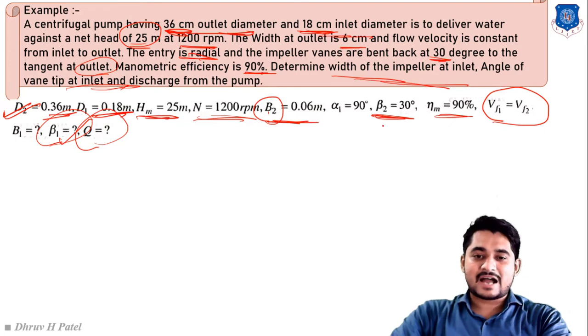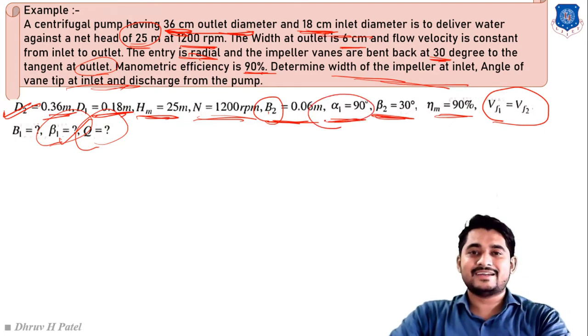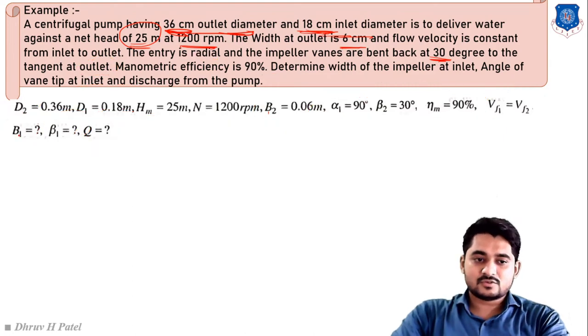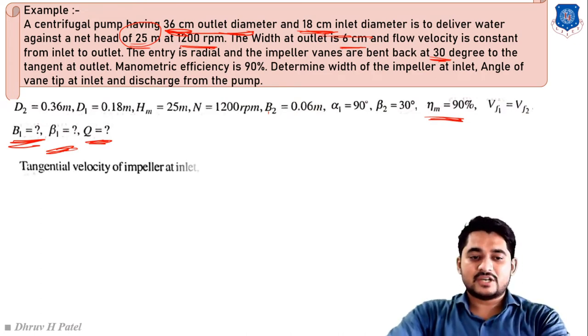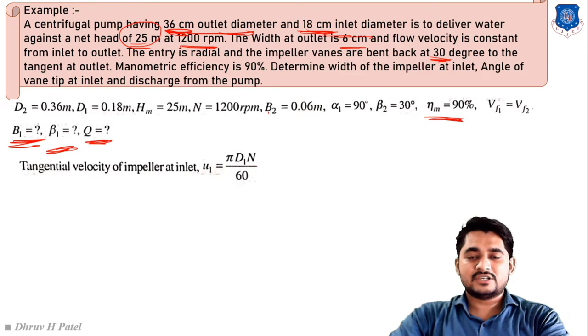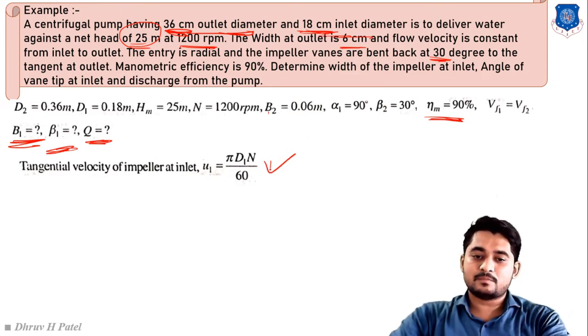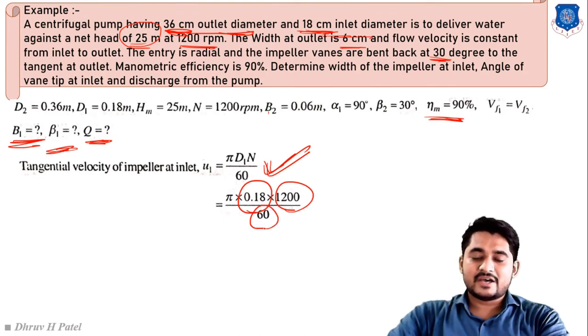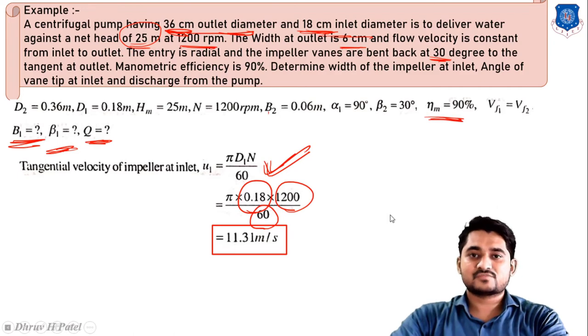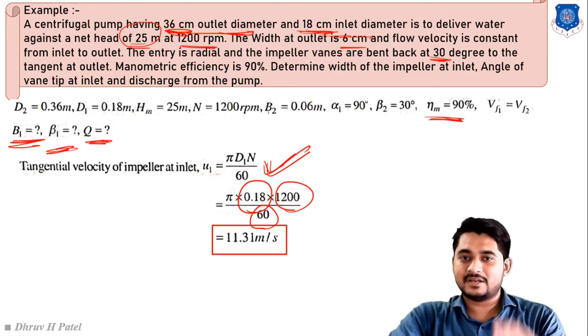For the centrifugal pump, α1 = 90° always. First, from the inlet velocity triangle, u1 = π d1 N / 60 = π × 0.18 × 1200 / 60 = 11.31 m/s, which is the tangential velocity of the impeller blade at inlet.